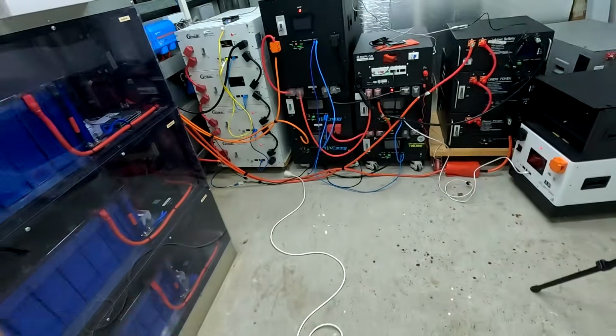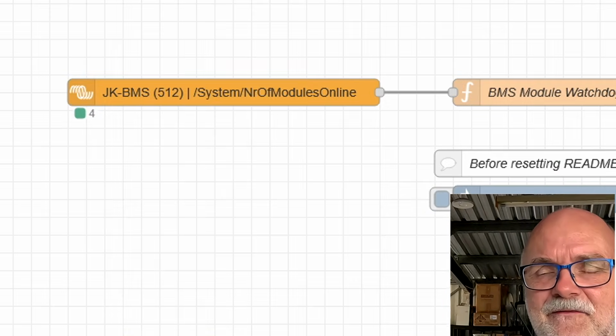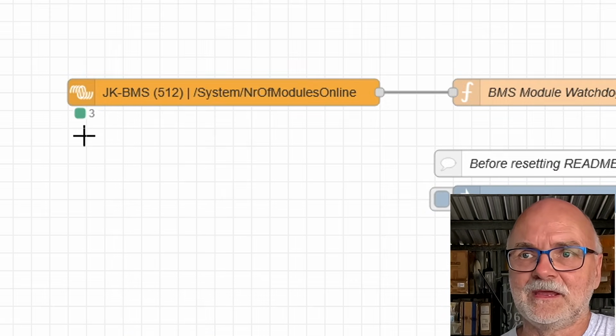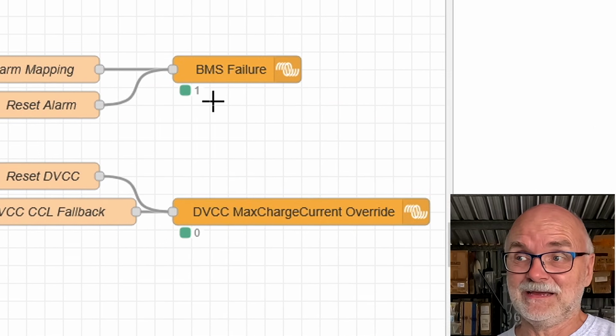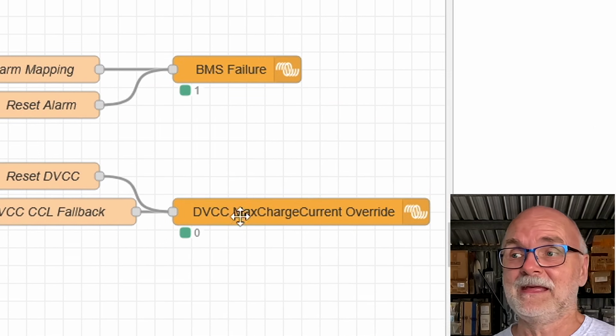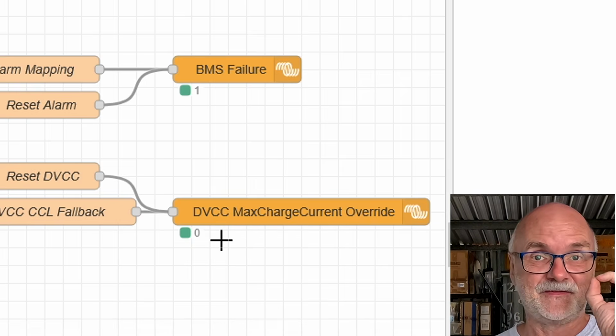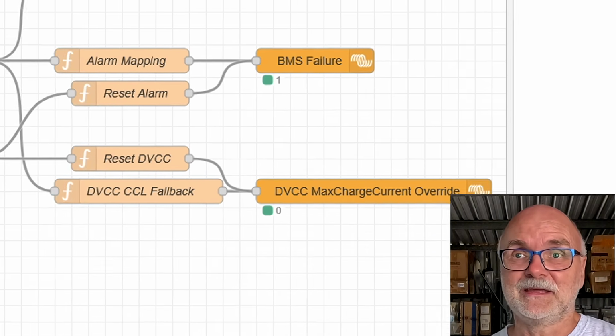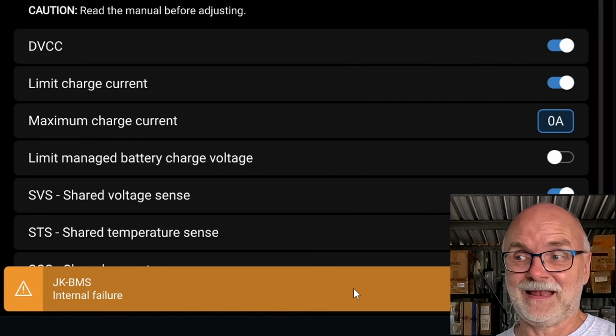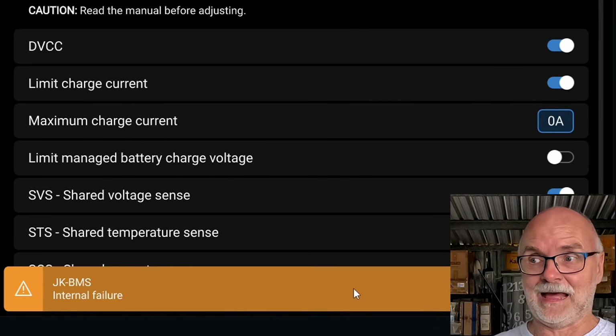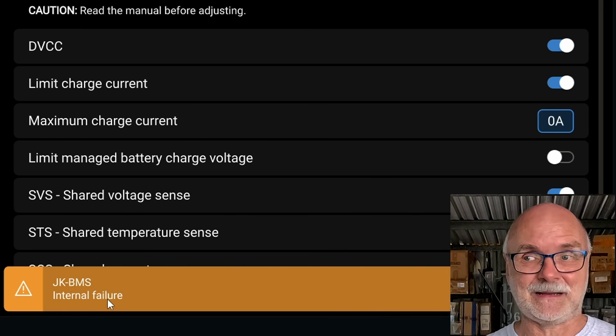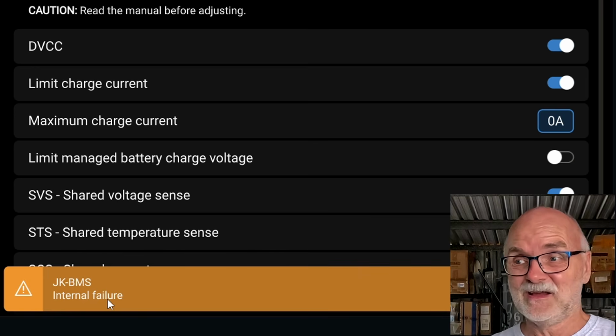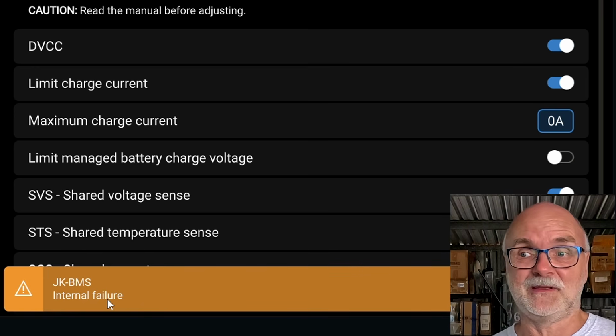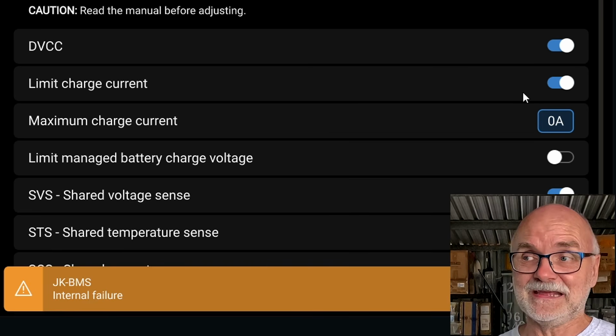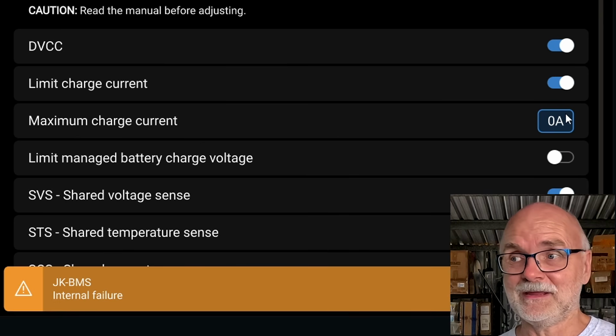So let's go ahead and disconnect one of the BMSs. Here in the workflow, we should now see on the left-hand side the number 4 going to number 3, just over here. It does it now. And you can see the BMS failure has now changed from 0 to 1, and the maximum charge current is now 0. That means 0 amps. If you have a look here in the Victron system again, first of all, we get an alarm now. One BMS has dropped out, and it says JK internal failure. Something is wrong with the whole stack of BMSs you had. We don't know if it's just a cable alarm or really one of the BMSs is faulty. We don't know. And you can also see the limit charge current is now turned on and the maximum charge current is 0.